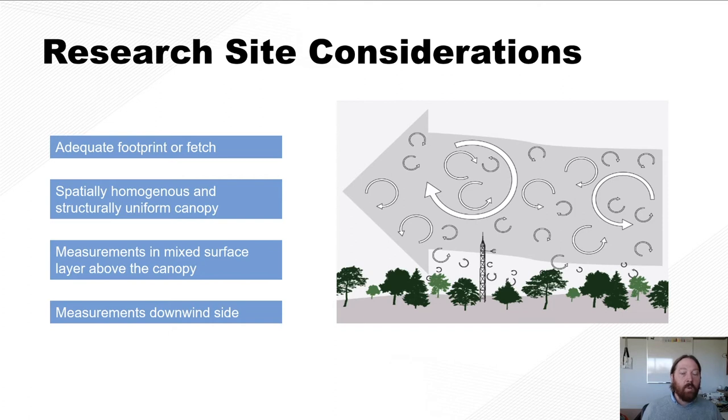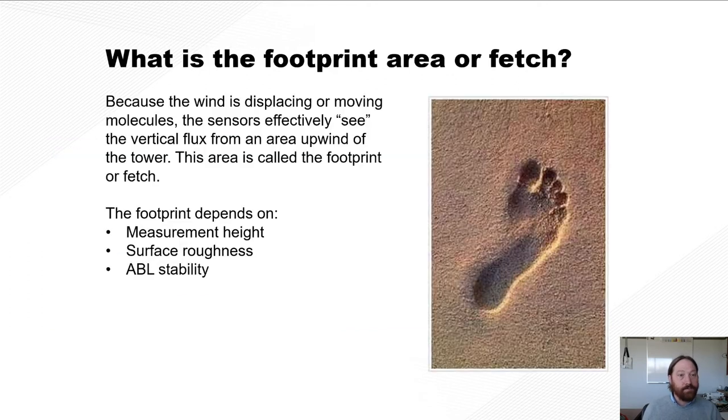And that the measurements are on the downwind side of your zone of influence. So in other words, what you want to measure is upwind of your tower, and your sensor is placed downwind of that.